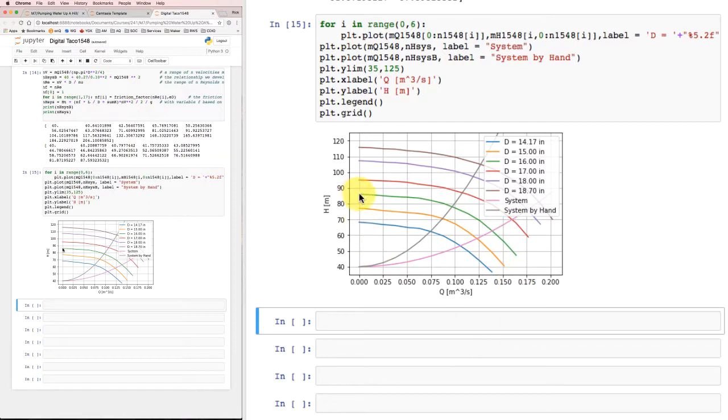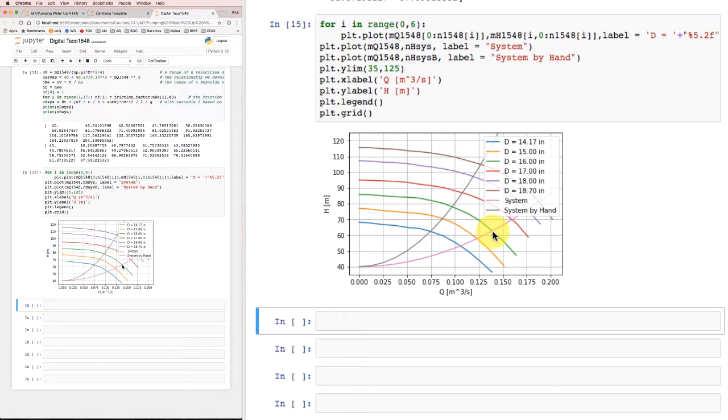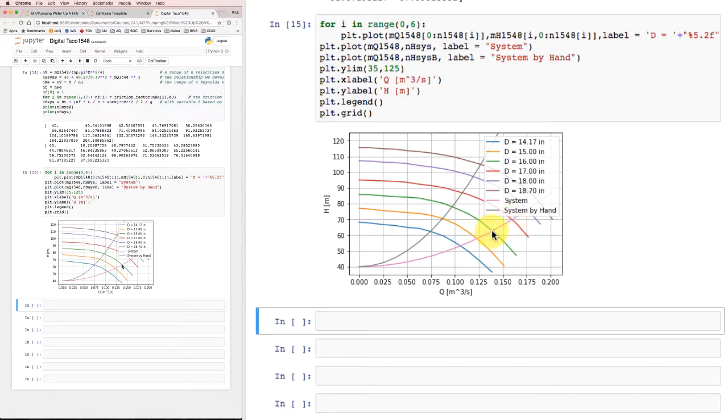So suppose we'd taken this 16-inch impeller and we bought that because it got pretty close to our design requirement, and I'd then gone up to an 8-inch pipe when I did the actual build. Well, in that case, I'd operate here where the 16-inch impeller line intersects our new system curve and I'd wind up delivering about 0.14 cubic meters per second rather than the 0.1, which was my design.